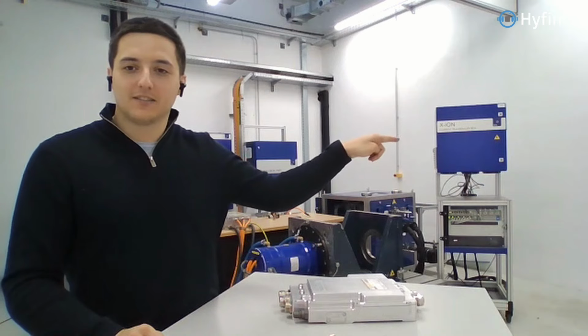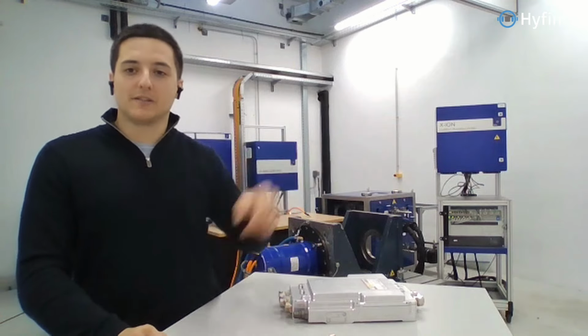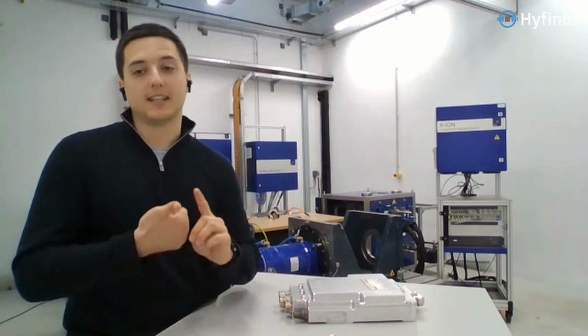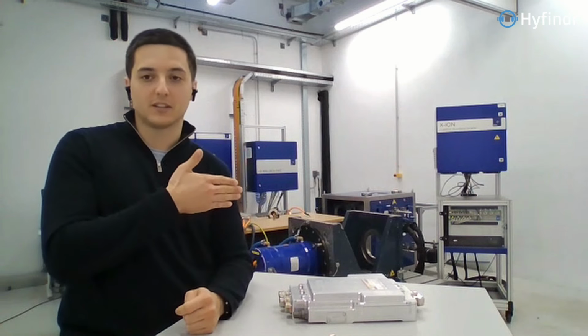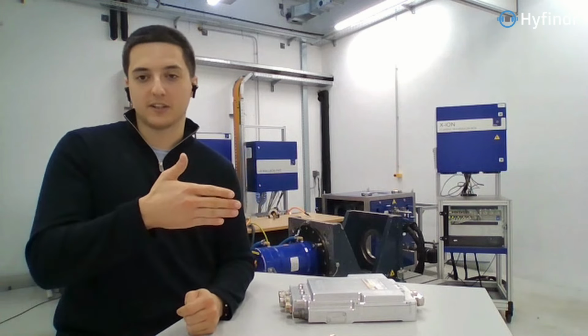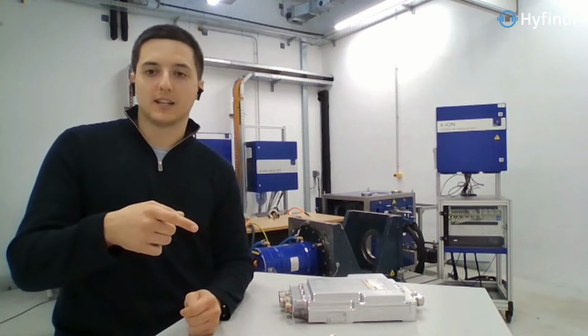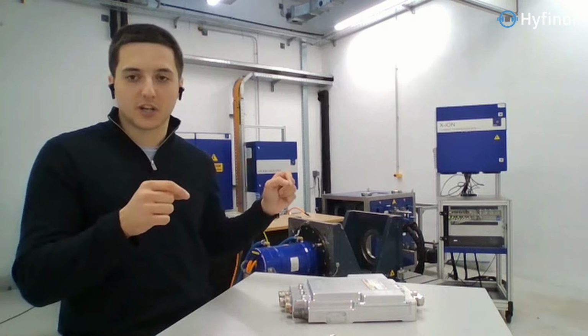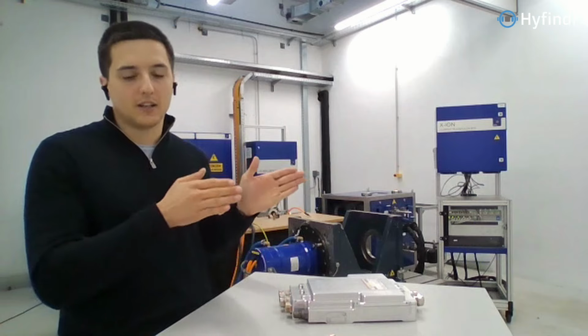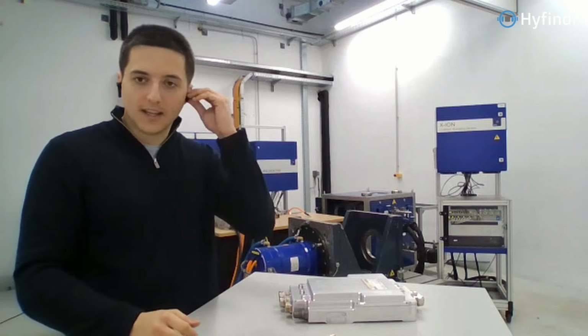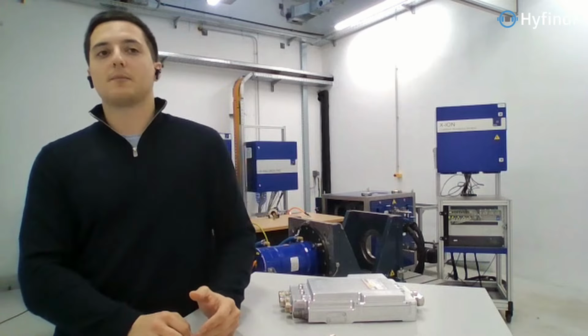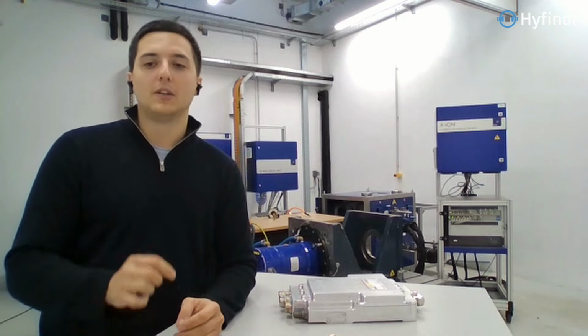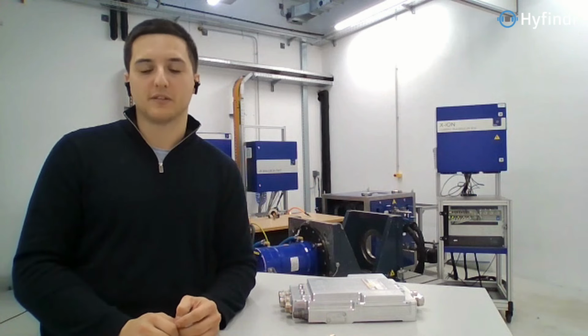Following the line, we have this device here - this is a power analyzer. It measures current on the DC side, before the inverter, so current and voltage before the inverter, and measures current and voltage after the inverter, on the AC side, as well as torque after the motor. With this measurement chain we can measure the efficiency of each component and of the entire subsystem at high speed - we're making measurements up to 2 megasamples per second, which is very fast sampling. With this information we can make a very accurate and precise calibration for the inverter.